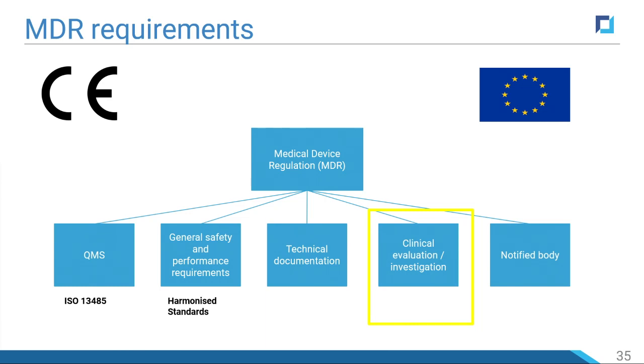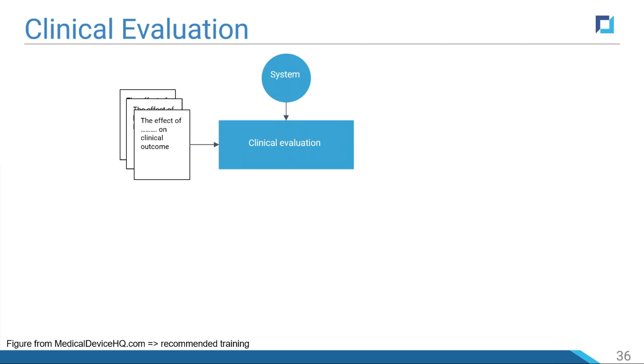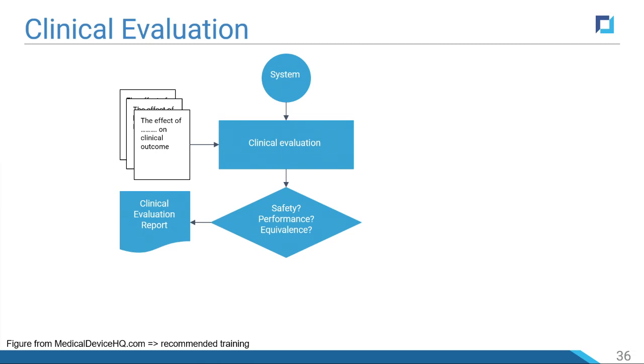Then regarding clinical evaluation, you need to demonstrate that your product has a clinical benefit and that it's safe. A lot of people think that if I develop a medical device, I also need to do a clinical investigation, but that's not true. In theory, if you find enough existing evidence in literature that demonstrates that your product is safe and performant, then you don't need to do additional clinical investigation. If you can demonstrate with existing information, that you generated yourself or that you find in literature, that the product is safe and performant, then you can simply make your clinical evaluation report.